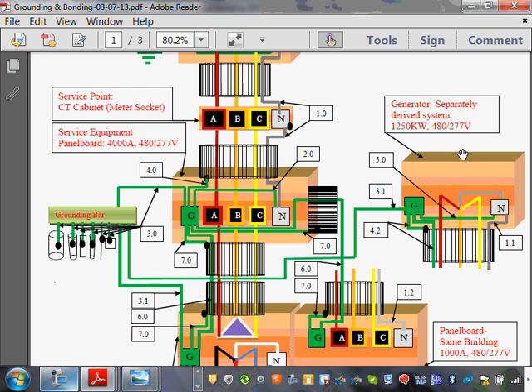Generators are completely different. Generators are voltage and power generators, so they can give you power at different voltage or the same voltage like in your system. Typically, if you have a generator, guys, if your system is 480 and your generator is 208, that's a mismatch. Then what do you do? You put in a transformer and step it up. But typically, if your system is 480, you have a 480 generator.